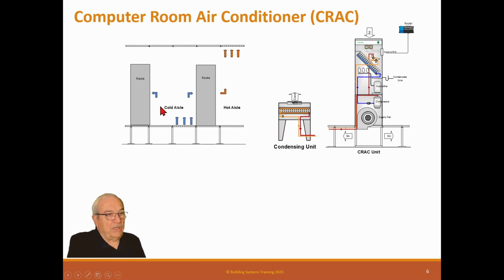And it can be cold. It can be 68, 65 degrees. You can feel it when you're here. And then it comes out a hot aisle, and over here it may be 80 degrees. Much more comfy. But remember, we're not cooling for people, we're cooling for the machines. And this rises. In most normal rooms, in the past, we've just let this air drift over to be sucked out of the room from this return.